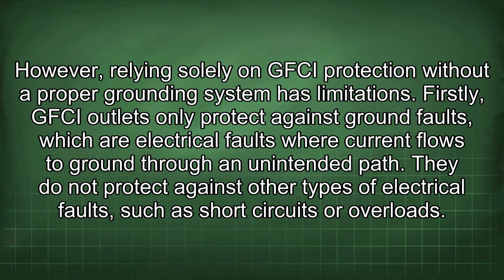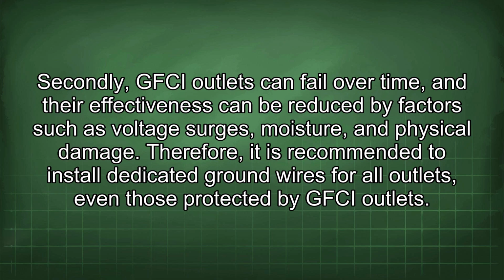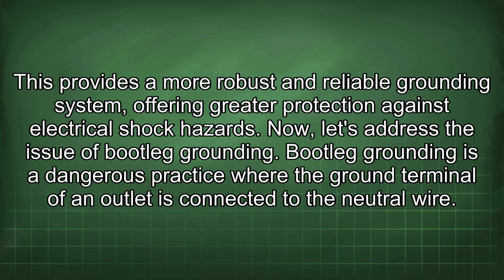However, relying solely on GFCI protection without a proper grounding system has limitations. Firstly, GFCI outlets only protect against ground faults, which are electrical faults where current flows to ground through an unintended path. They do not protect against other types of electrical faults, such as short circuits or overloads. Secondly, GFCI outlets can fail over time, and their effectiveness can be reduced by factors such as voltage surges, moisture, and physical damage. Therefore, it is recommended to install dedicated ground wires for all outlets, even those protected by GFCI outlets. This provides a more robust and reliable grounding system, offering greater protection against electrical shock hazards.